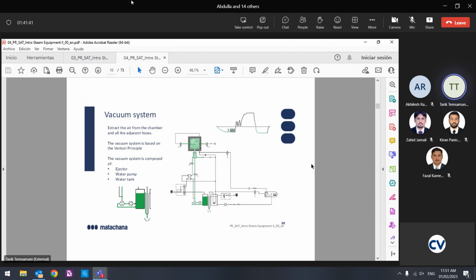Okay. So I will now give you some examples of what can happen if we have any problems. So, what is the vacuum system? Basically, it is to extract the air from the chamber and all the adjacent hoses. The vacuum system is based on the Venturi principle. The Venturi is the ejector. The vacuum system comprises an ejector, a water pump, and a water tank. Okay, these are the components. Now, I start my vacuum. First, what is the pressure I have to reach in the steam sterilizer for the vacuum? You remember or not?